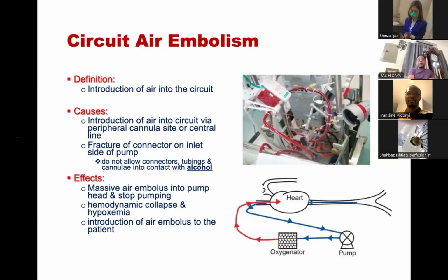And I highlighted here especially, do not allow connector tubings and cannula to come into contact with alcohol. So don't swipe your connector and tubing with an alcohol swab. Avoid this, otherwise it can create a problem for you. What can be the effect if you get air in the system? Massive air embolism into the pump head and the pump stops pumping. Of course, the flow starts fluctuating. If you get a huge amount of air, you are not able to achieve the flow which you require, and it starts fluctuating.